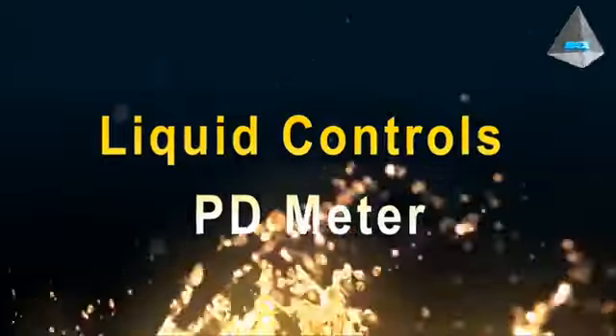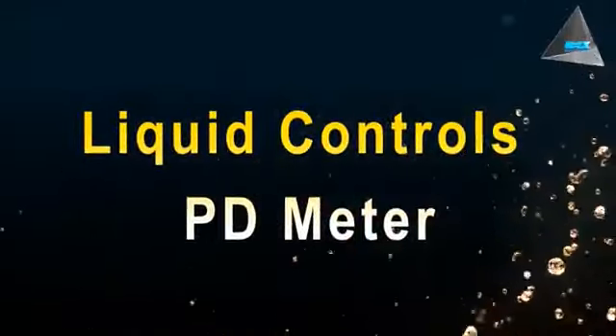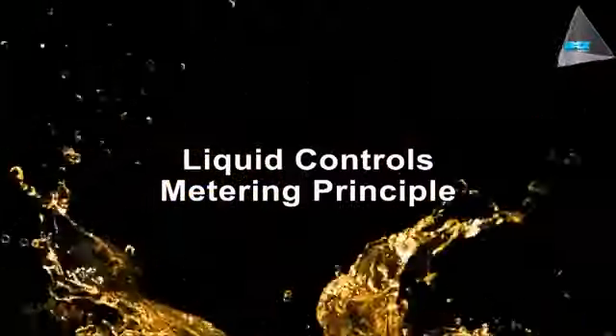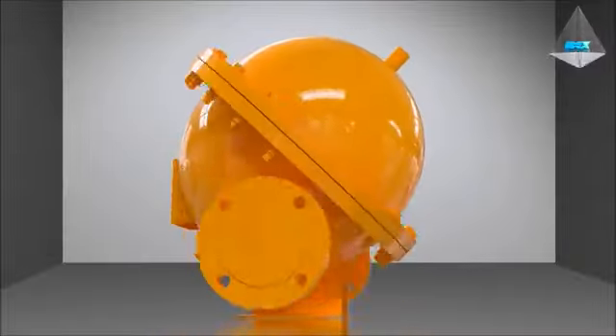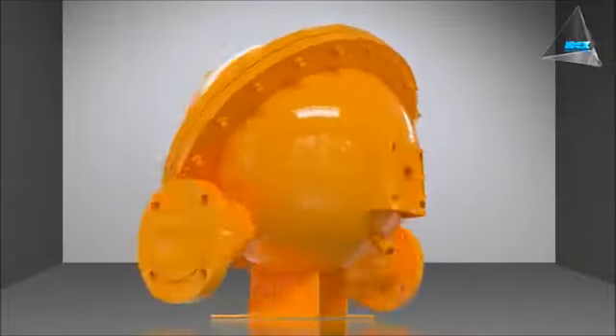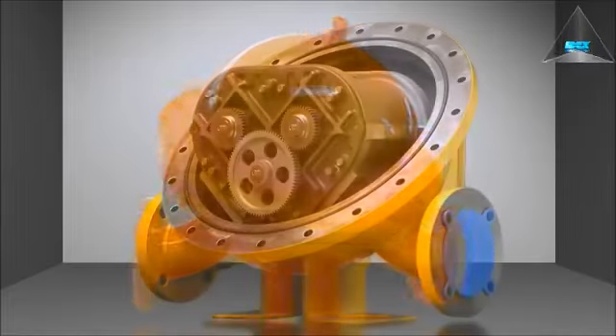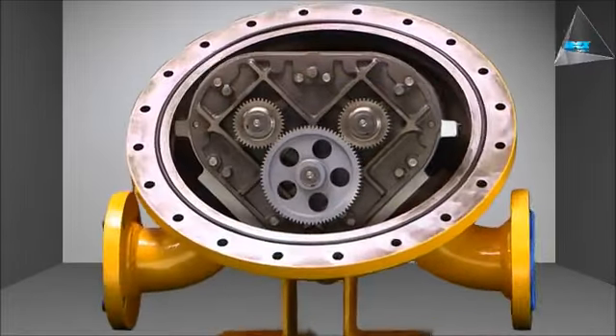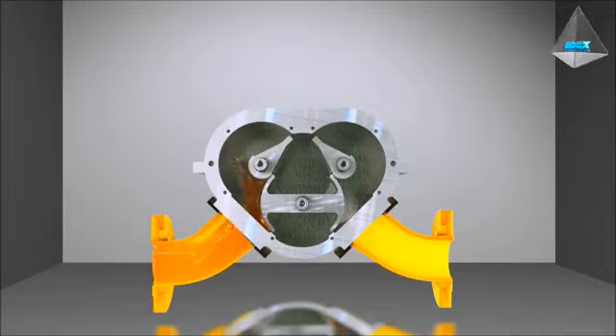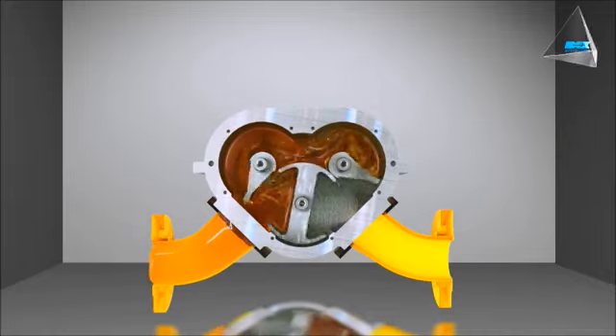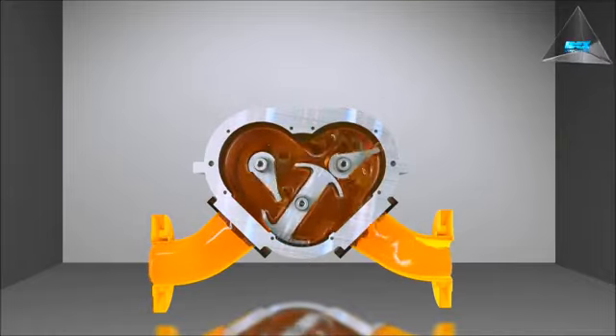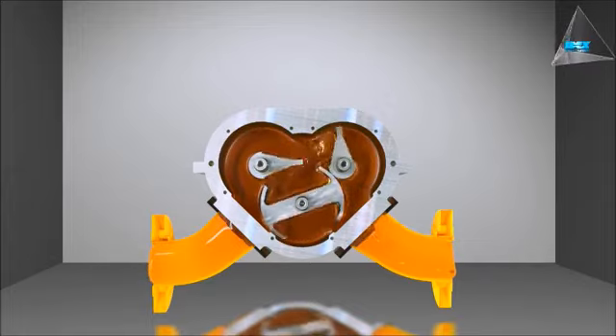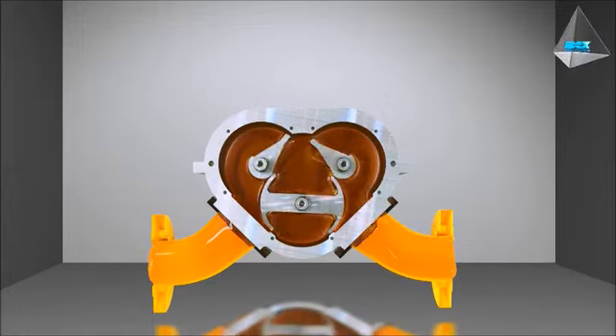Liquid Controls PD meter. The Liquid Controls metering principle. A Liquid Controls positive displacement flow meter is, in a sense, a hydraulic motor with high volumetric efficiency that absorbs a small amount of energy from the flowing stream. This energy is used to overcome internal friction in driving the meter and its accessories.